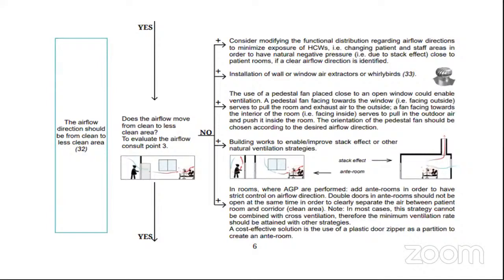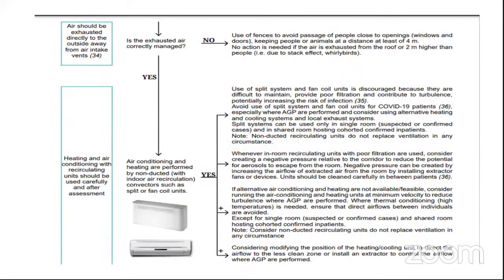One cost-effective solution that has been given is the use of a plastic door zipper as a partition to create the ante-room. If the airflow is from clean to less clean area, we need to ask the next question, which is: is the exhausted air correctly managed? According to the guidelines, air should be exhausted directly to the outside, away from air intake vents. People should be at a distance of a minimum of 4 meters, and the air should be exhausted from the roof or at least 2 meters above where people are. Whirlybirds or a stack effect could be used.